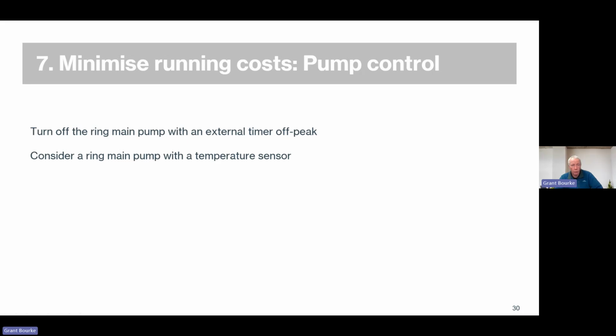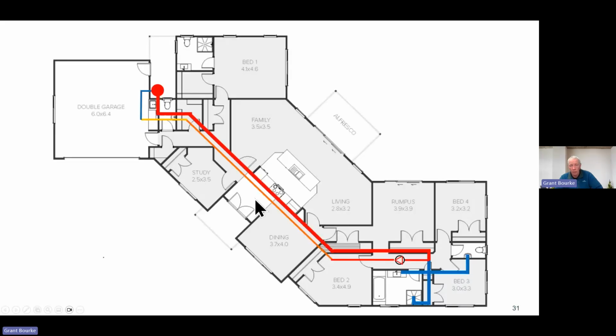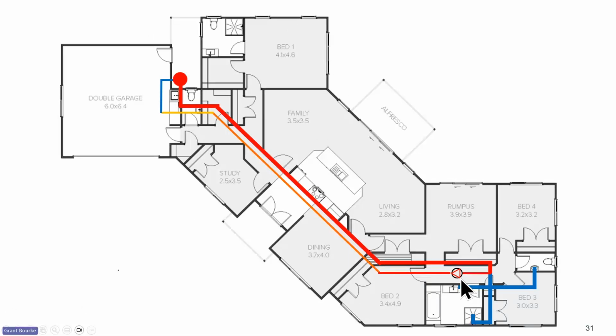Consider a ring main pump with a temperature sensor. I'll talk about that in a second. What we can do with that is shift our pump down to just past the furthest offtake point. If it's got a temperature sensor, the water will flow around. The pump will know when it's up to temperature, and it will turn off, and it won't fully heat the ring main return. When the water cools down a little bit, the internal temperature sensor on the pump notes that, and it turns the pump on again for a short period till the temperature rises again.